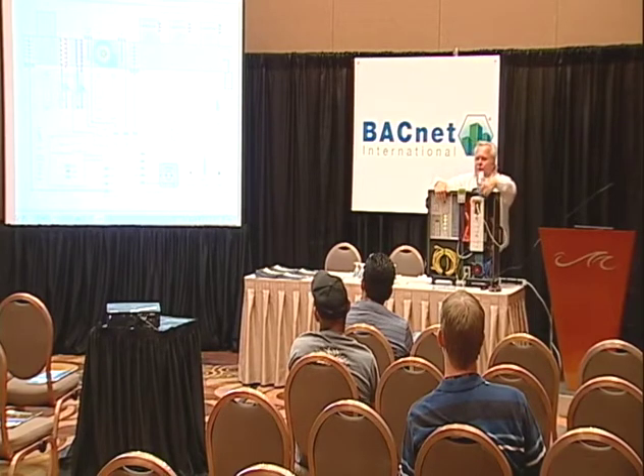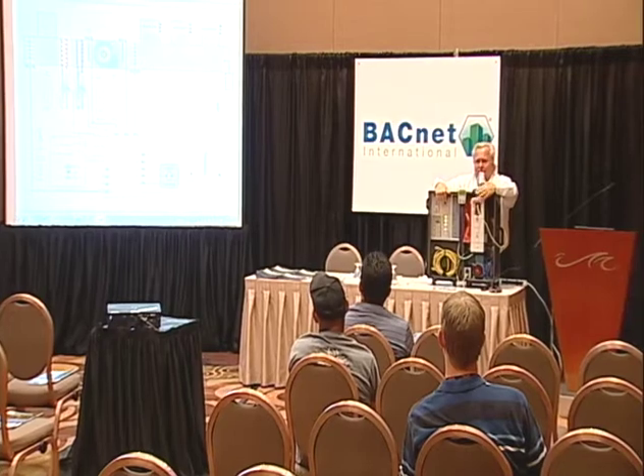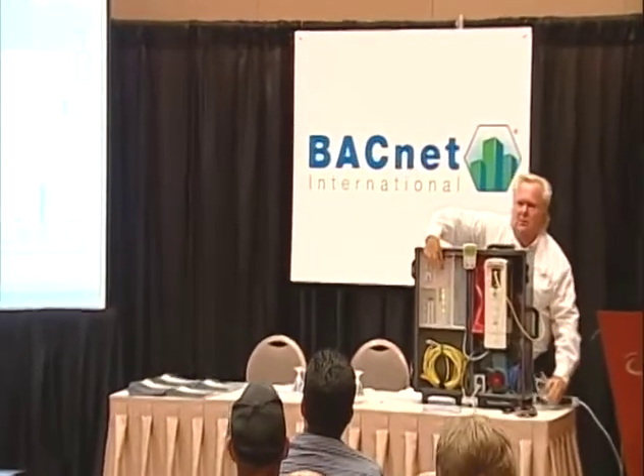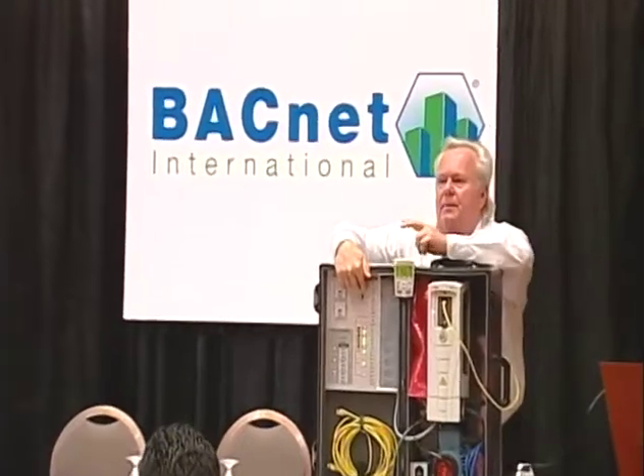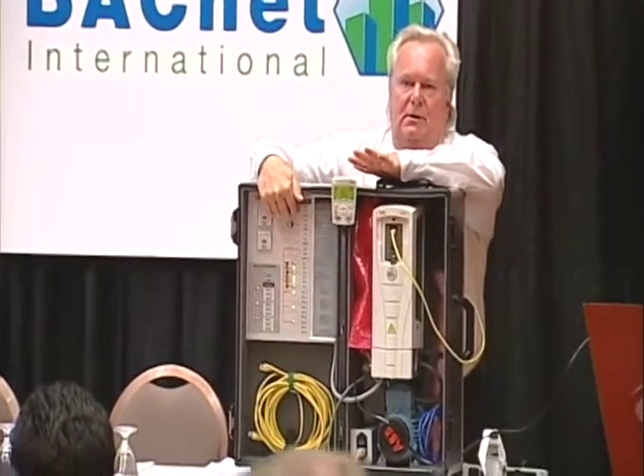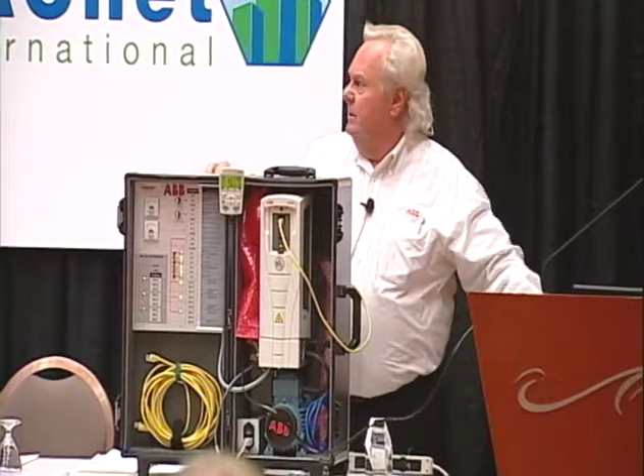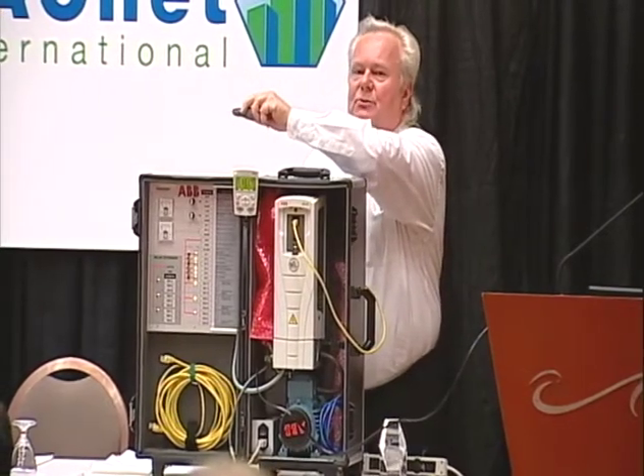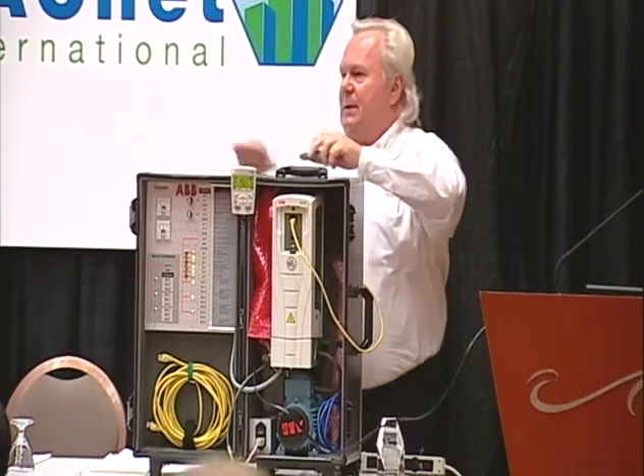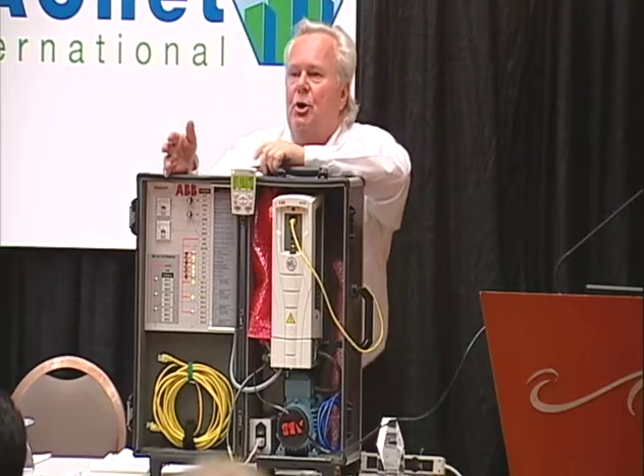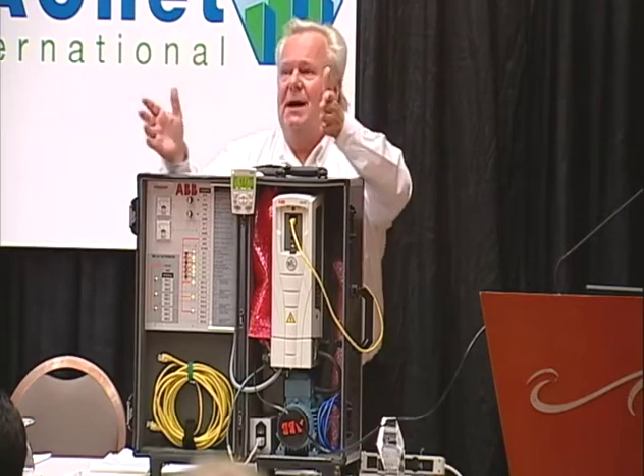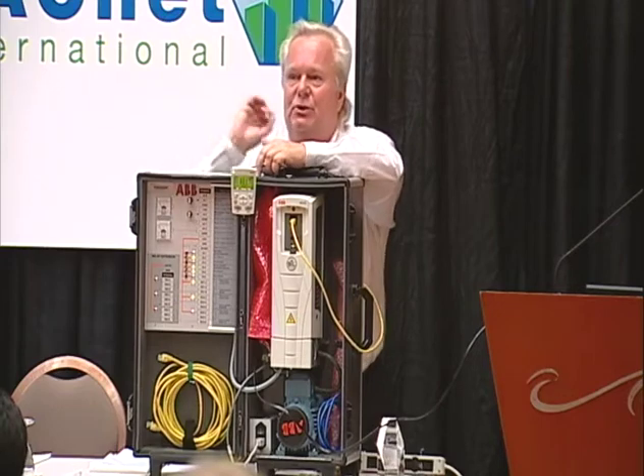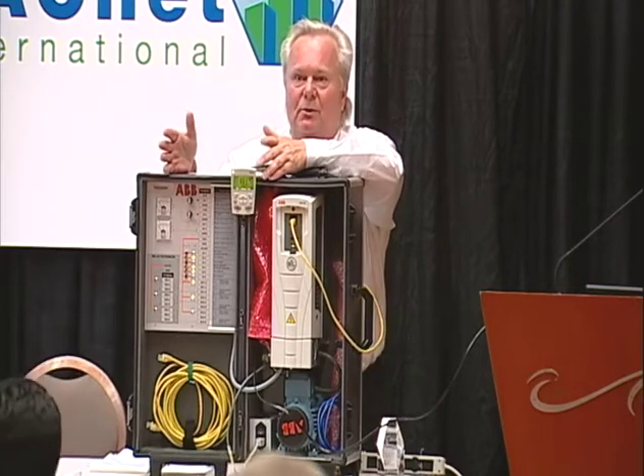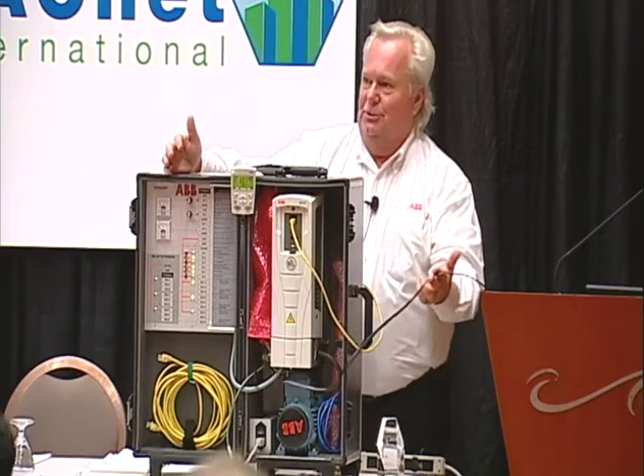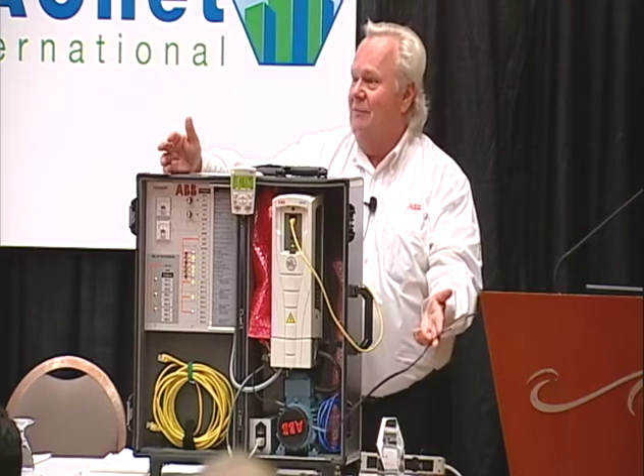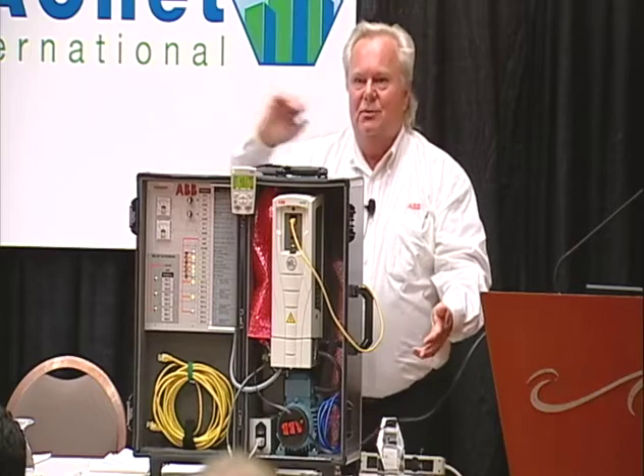So once again, I'm doing the math, the PID loop, in the VFD. Okay. So the reason for that is twofold. Number one, network traffic. If I'm doing the math here in a building automation system, I'm doing the PID loop there and sending a speed command to the VFD, I can do that. But if I'm trying to keep a nice constant static pressure in this room, I might have to send it a new speed command every second. Well, there's other important stuff on this wire like chillers and pumps and all sorts of other stuff. I don't want to needlessly send traffic.